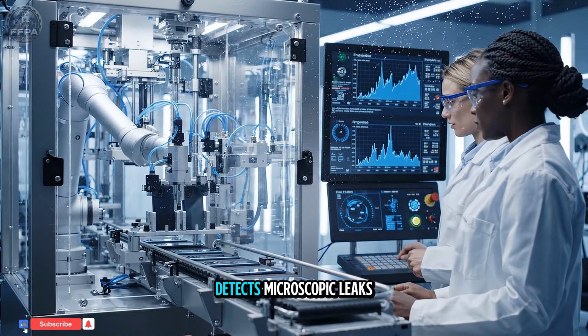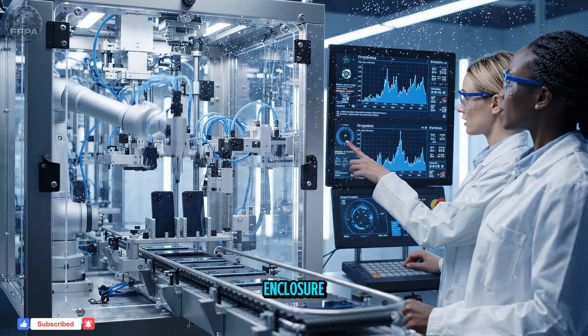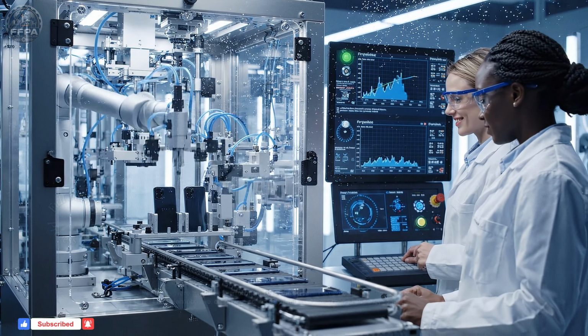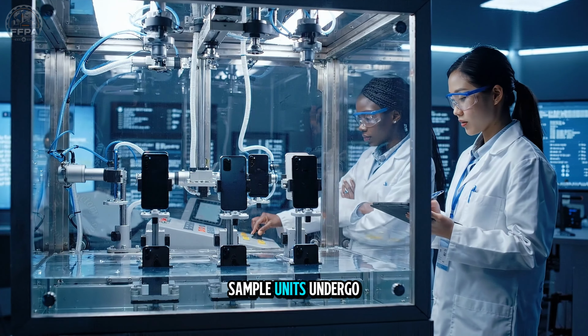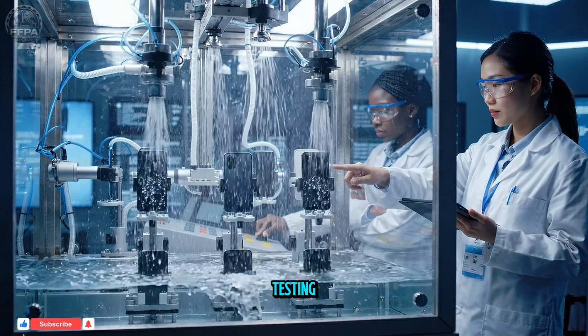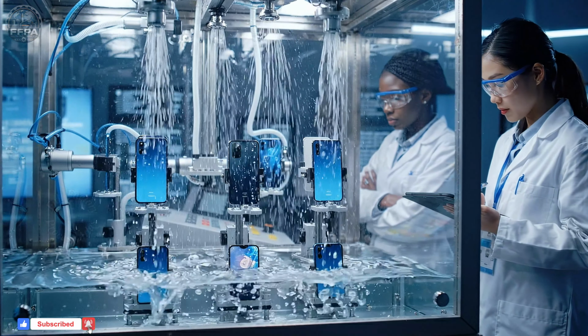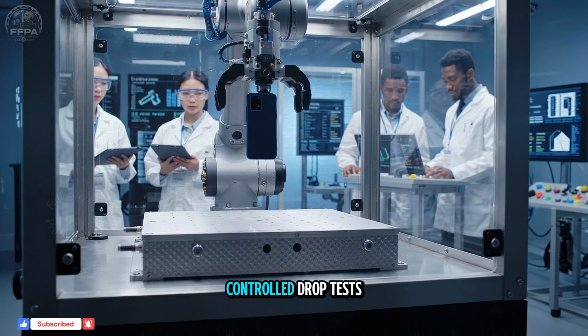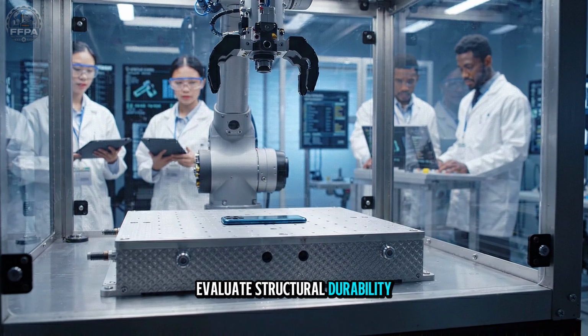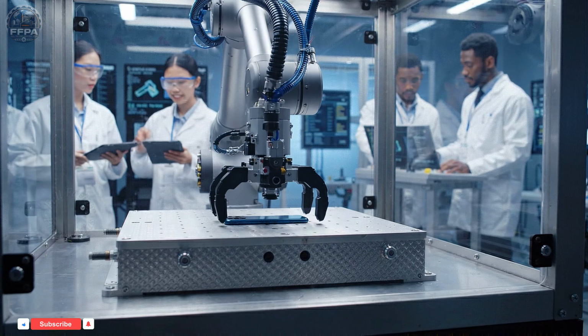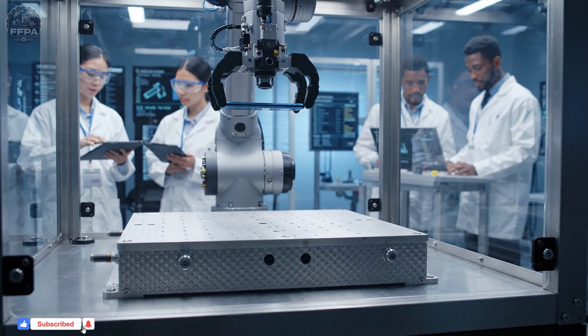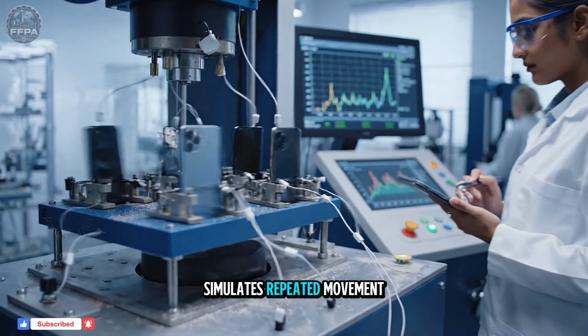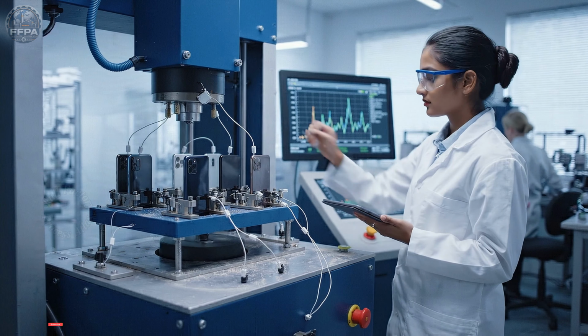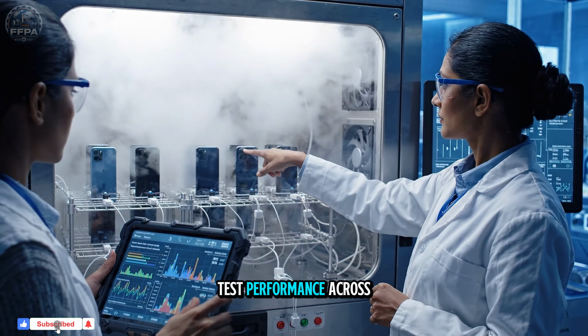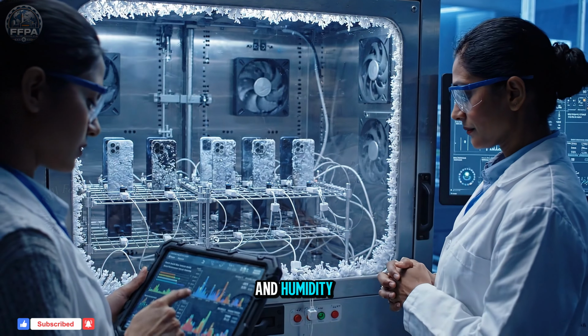Air pressure testing detects microscopic leaks in the sealed enclosure. Sample units undergo validated water resistance testing. Controlled drop tests evaluate structural durability on selected samples. Vibration testing simulates repeated movement during transport and daily use. Environmental chambers test performance across changing temperature and humidity.